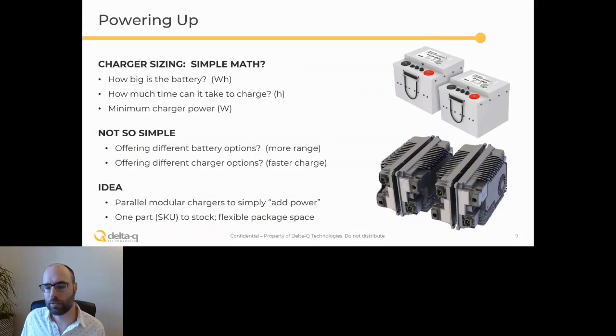So they're looking at EVSEs - well, they're looking beyond the EVSEs and more into DC fast charger territory. And less than 5% is looking for over 100 kilowatts, so that'll be some of those Scania trucks, I expect. So that 1 to 3 kilowatt range, and then 3 to 10 kilowatt range, that's really where you see the break point between using a residential outlet maxing out at 1.5 to 2.5 kilowatts, depending on the continent, up to needing a single phase or even a 3-phase connection at an EVSE or an industrial plug.